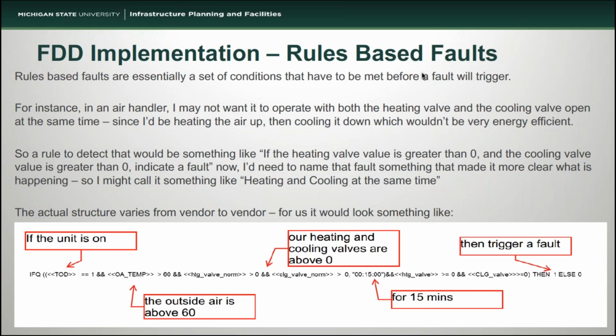So a little bit on what a rules-based fault is. It's really just a set of conditions that have to be met before a fault triggers. You can think of it as an alarm. In this particular instance, with an air handler, it's not as efficient to operate an air handler when you're both heating and cooling at the same time. So an example of a rules-based fault would look at, is my heating valve open and is my cooling valve open at the same time? And if so, trigger a fault, because that's an inefficient operation.